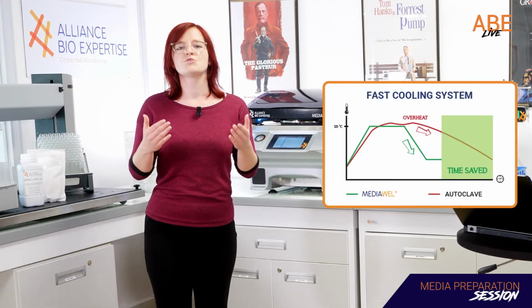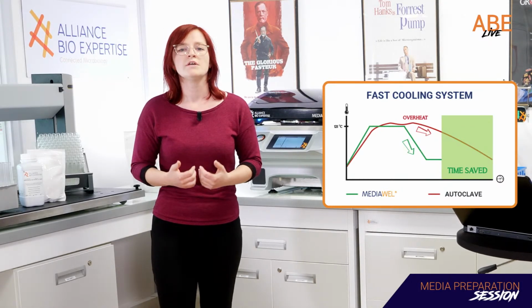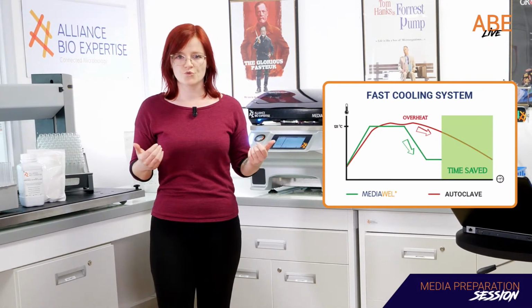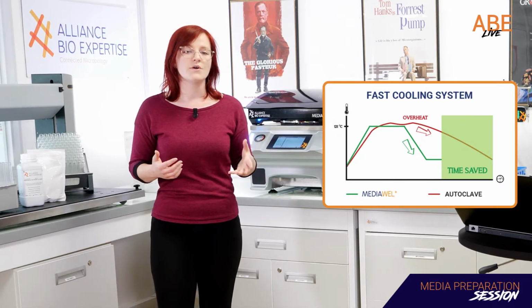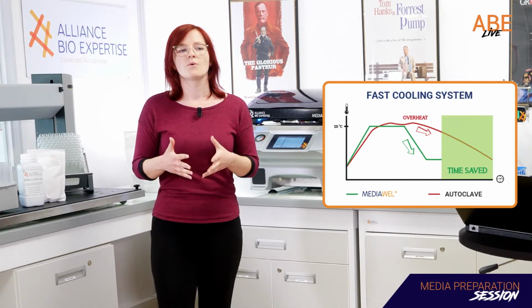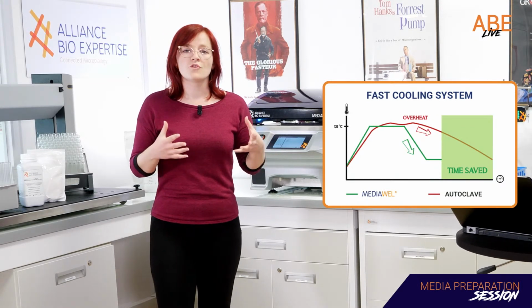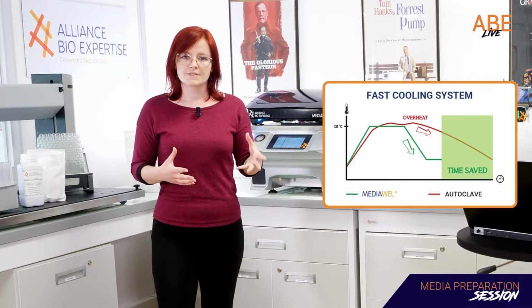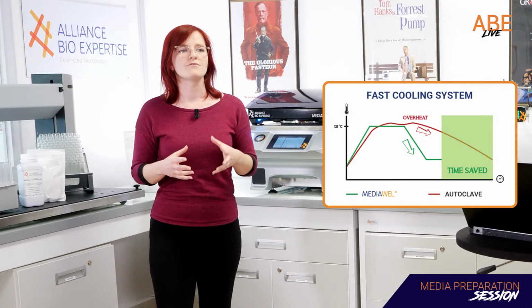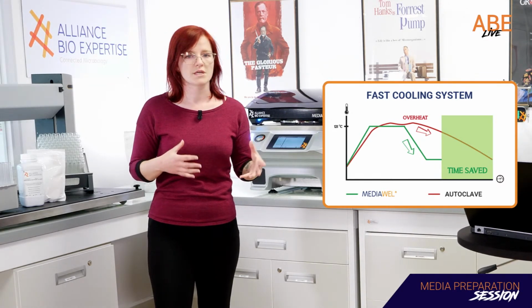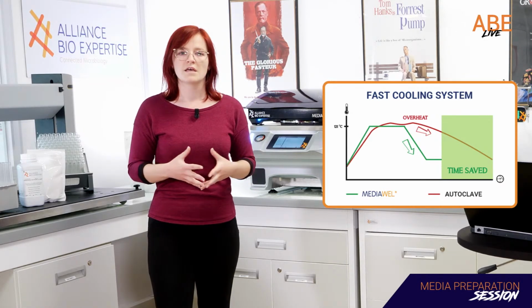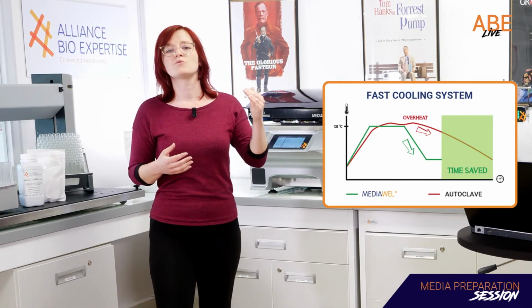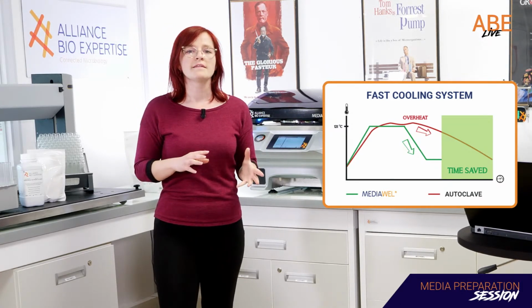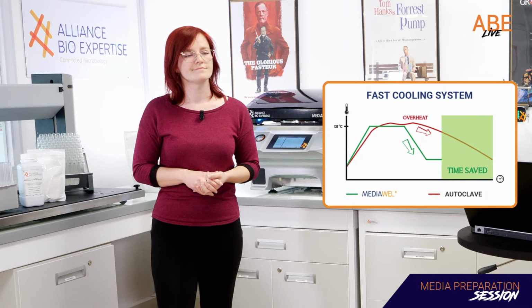Knowing that in the autoclave, for most of them, you don't have any fast cooling system, so you need to wait for the temperature to go down naturally. So it means that it will take around 2 hours. When with a media preparator, you have a fast cooling system. So first, it will depend on the volume you prepare. If you go for 1 liter, for example, it will take around 50 minutes. And if you go for 30 or for 50 liters, it will take around 90 minutes. And then, thanks to the fast cooling system, you will be able to distribute at the right temperature in 15 or 20 minutes maximum. Okay.